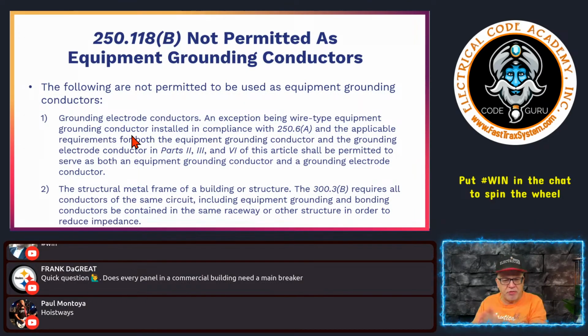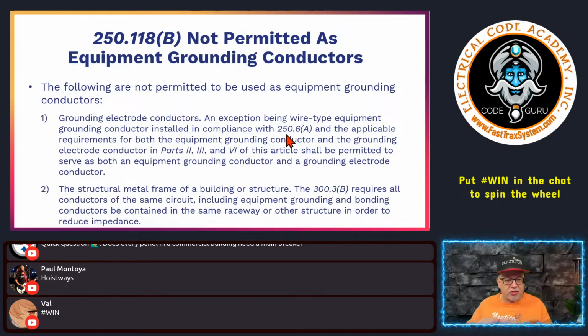Now, there is an exception if you're using the wire type, okay? So if you're using a wire type, then the exception says if it's a wire type equipment grounding conductor installed in compliance with 250.6(A), which again is talking about not creating objectionable currents, okay? So we can't have that problem. It says if you can do it and you don't have objectionable current issues, and the applicable requirements for both the equipment grounding conductor and the grounding electrode conductor in parts 2, 3, and 6 of this article shall be permitted to serve as both an equipment grounding conductor and a grounding electrode conductor.